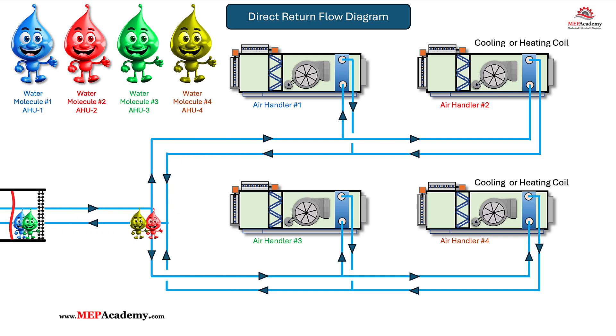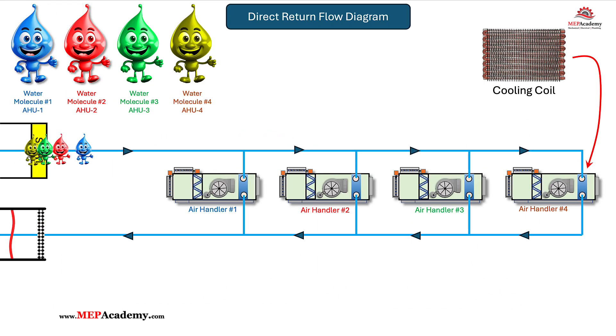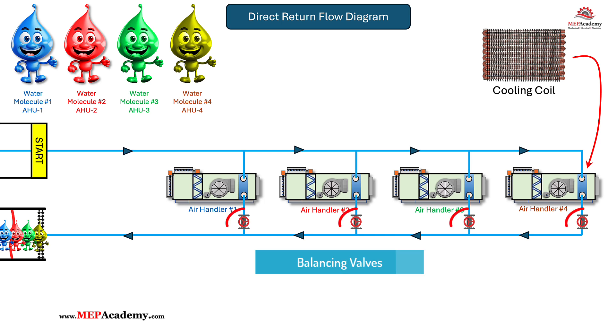Since the closest air handlers have less piping, they'll have less pressure drop — considering the pressure drop for all coils is the same. This creates different pressure drops for the piping circuits to and from each air handler, which creates a water balancing issue.